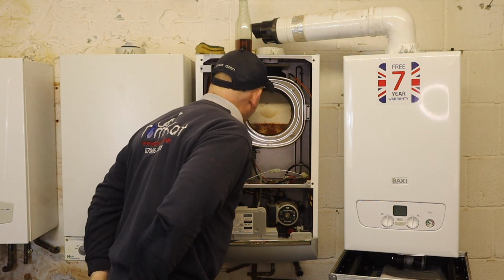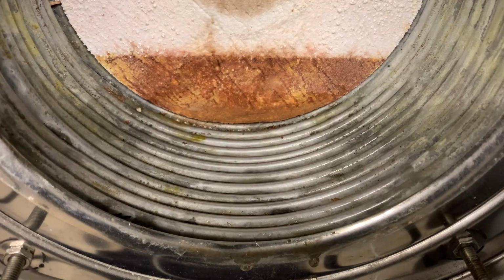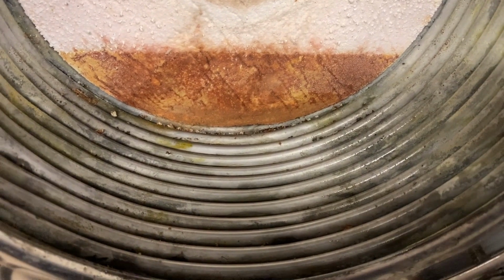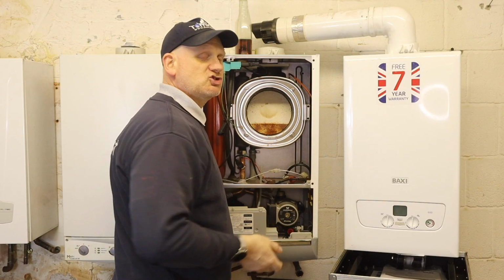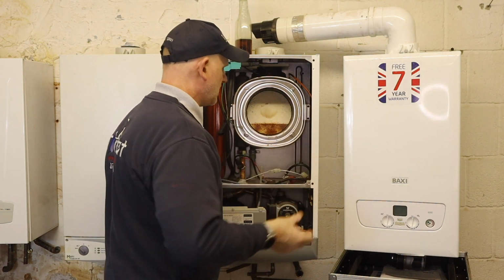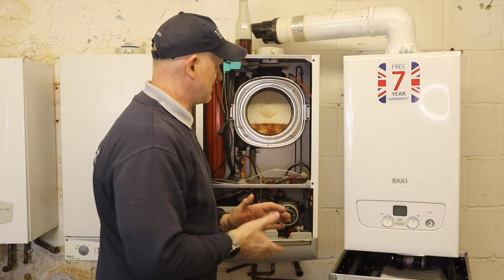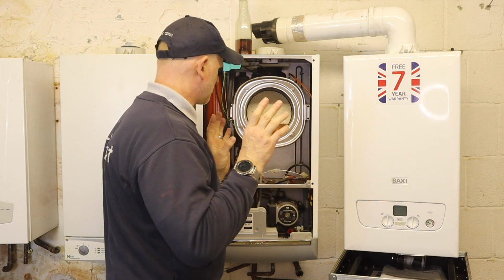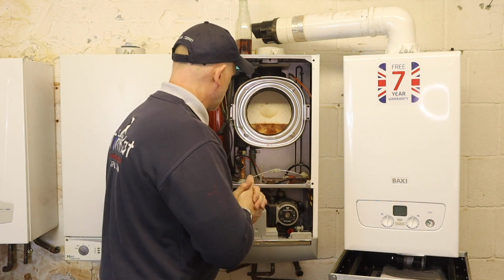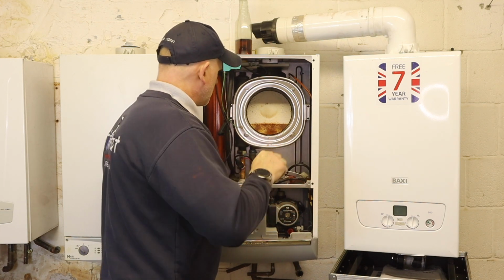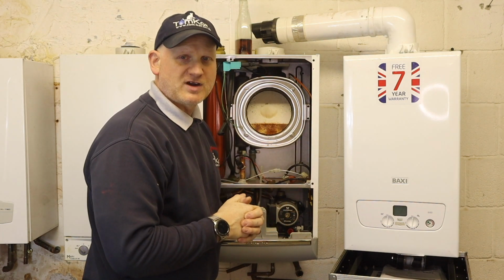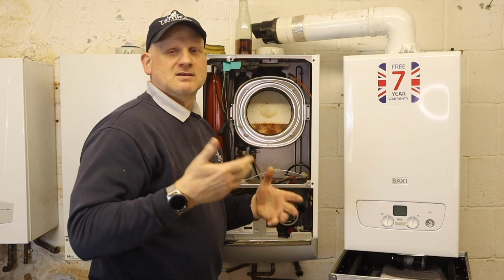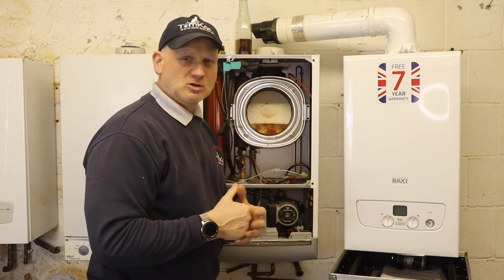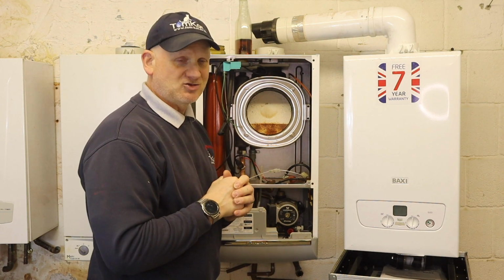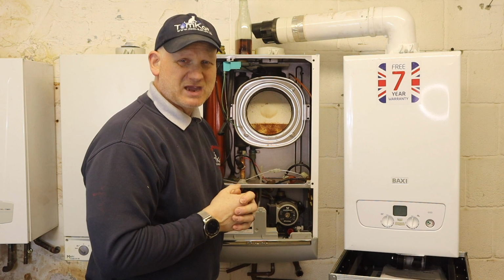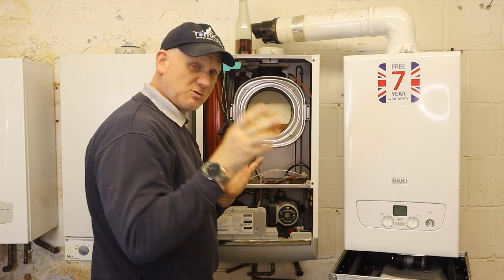Well, I can pretty much say that has worked pretty well. Now obviously I would have to make sure that I wash all that through because it is acidic at the end of the day - not as acidic as white vinegar, but still acidic. So make sure you flush loads of fresh clean water around it, otherwise you're going to end up getting pinholes in your stainless steel heat exchanger. But this 50-50 mix shouldn't make much difference as long as we wash it away.